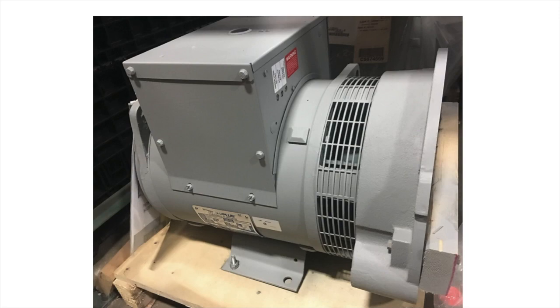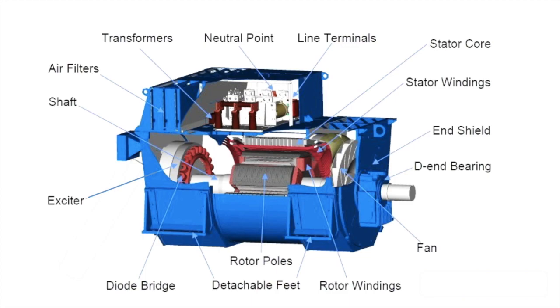and here you can see the cut section of the alternator where you will find all the parts: the exciter, the shaft, air filters. It is for a diesel generator, therefore there will be air filters. Then transformers to transform to the higher voltage, the neutral point because it is star connected, line terminals for the external connections, stator core, stator windings, end shield which acts as a frame and the bearing shield. The D end bearing, that means the driving end bearing. Then you have a fan, rotor windings, rotor poles, detachable feet, so that as per requirement you can have it, and the diode bridge is used with the exciter for rectification purposes.